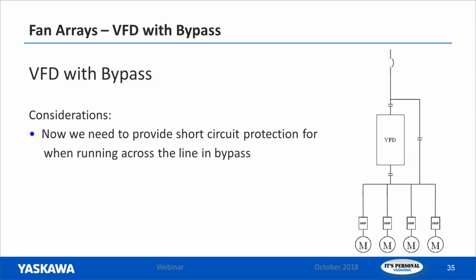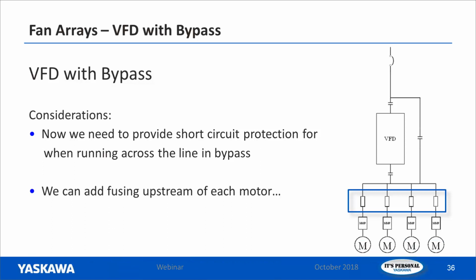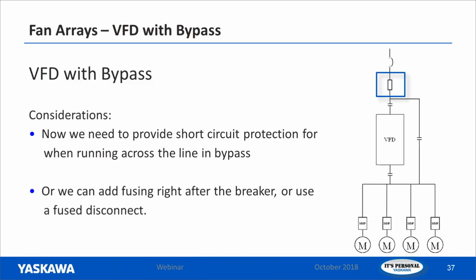But in this situation, now that we have a means of running the motors without the VFD, we're going to have the line power going directly to the motors. So we do need to provide short circuit protection for when running the motors across the line in bypass. So there we have our fuses. We can add them right upstream of each motor circuit, or we can have them upstream in the package. So we could add the fusing right after the breaker or use a fused disconnect.